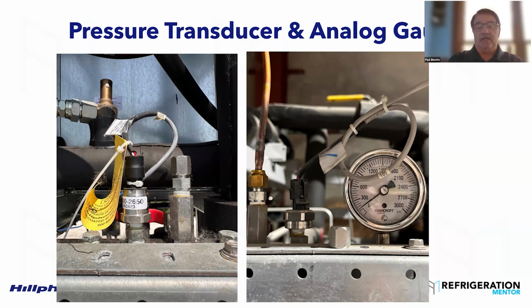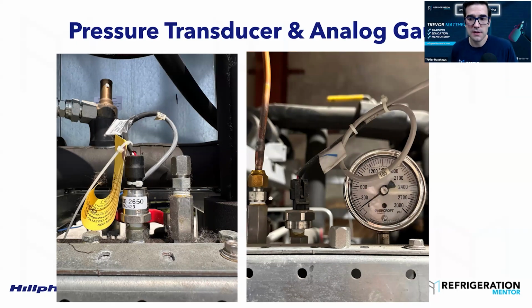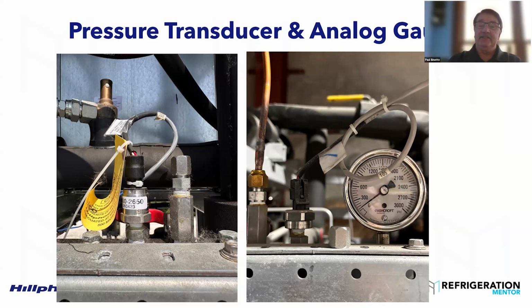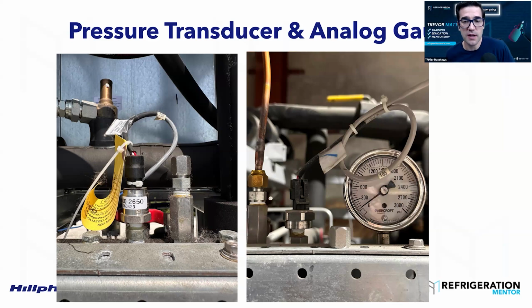All right. So when we're doing our checks, along with our solve the question: in the old days, you would start a compressor and close the discharge valve until you trip the discharge switch. Yeah, we don't do that on CO2. The way you test it is just take the screw out of it, pull the cap off, and watch your proof signal go to off for your compressor. There are still technicians I talk to, even on CO2, who do it the old way, but you need to know what you're doing. You have to do it safely. Yes, because in a very quick way, you can go very bad, and that 2155 relief valve on the front of that compressor can come right into your face. Yeah, right in your face. So you've got to know what you're doing if you're doing it that way.